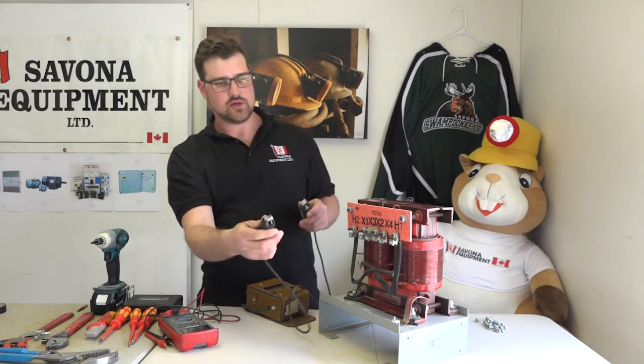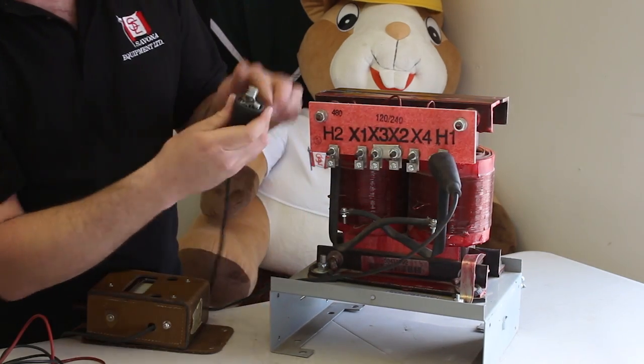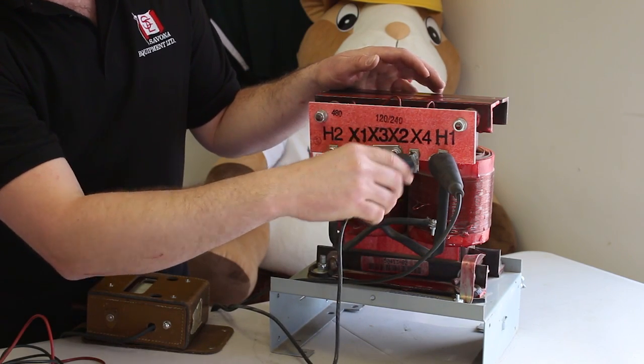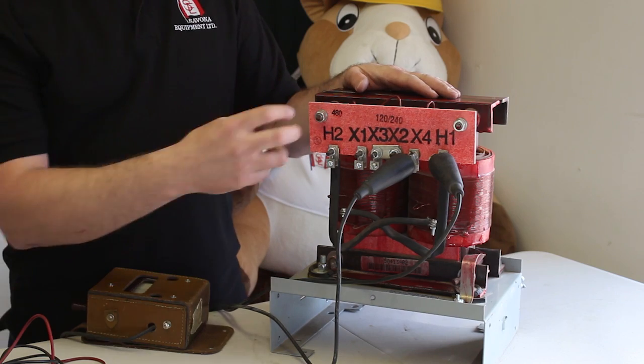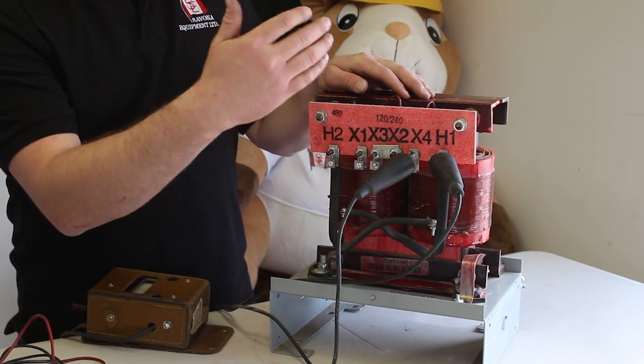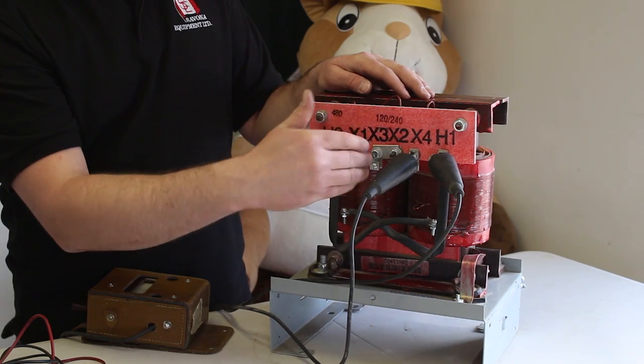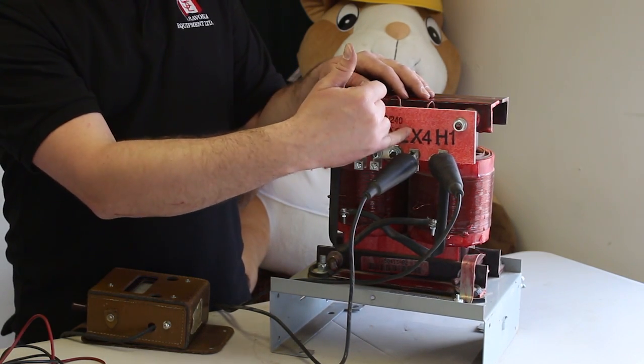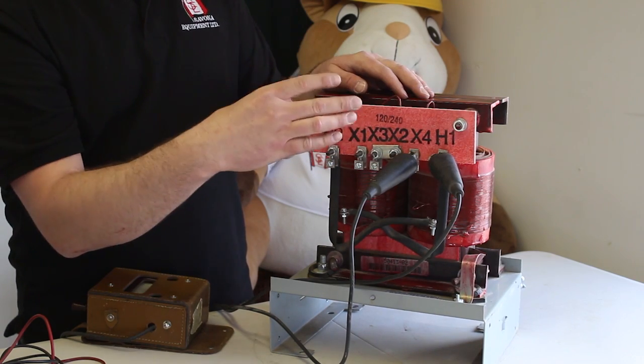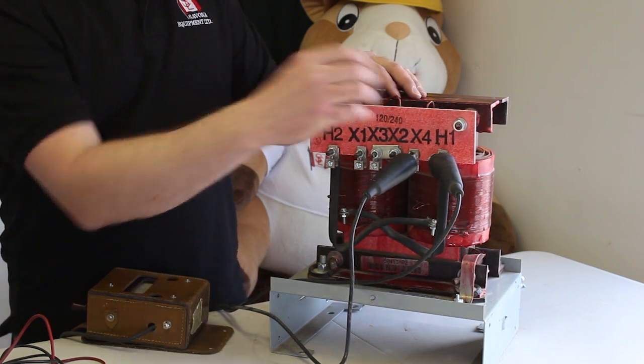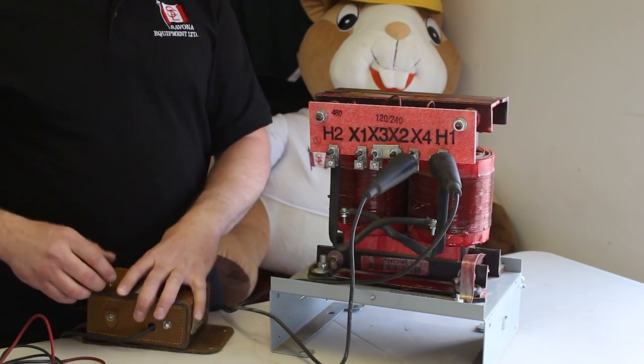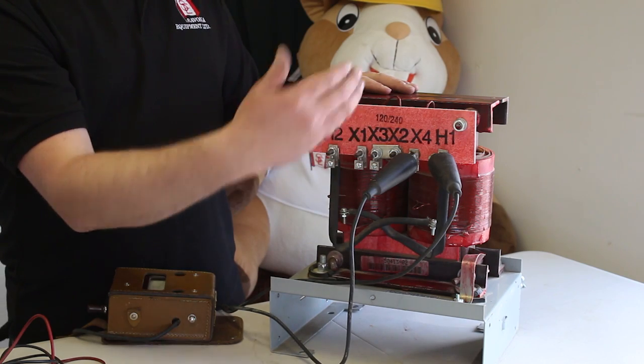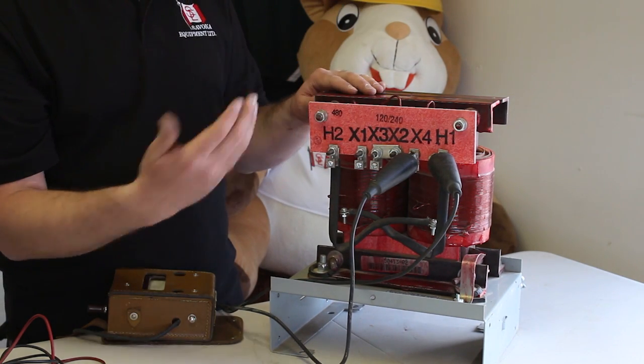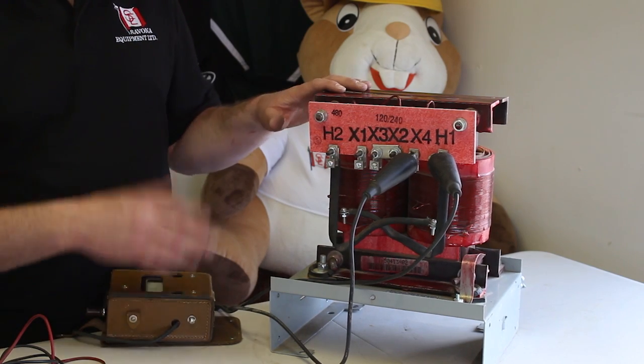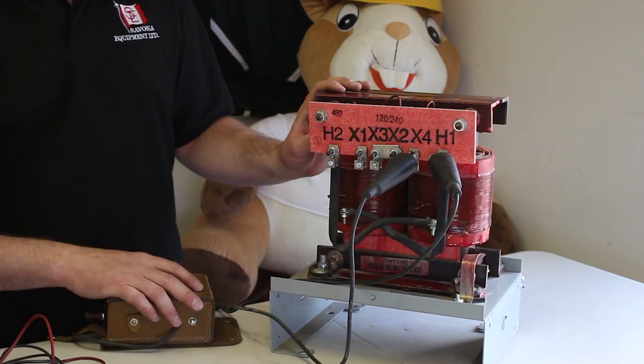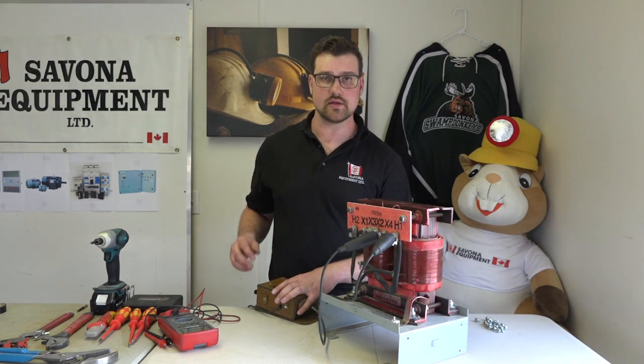So I'm just gonna take my 2 leads here, hook one up to H1 and then one to one of the low voltage windings. And we don't need to megger each individual winding here, or individual termination point, because we already know that there's continuity between our low side and continuity through our high side, so they're connected electrically. So doing this will tell us if the insulation ratings on this is good. I mean, you can test each one just to be safe. It's not going to hurt anything, but for this purpose, we'll just do the high voltage to the low voltage winding here, or primary winding to secondary winding.